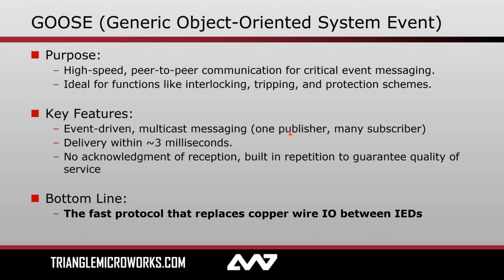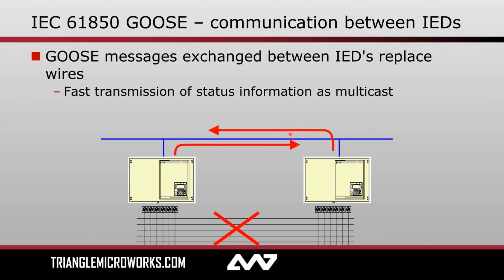But the bottom line, the thing that I hope you guys take away, if you haven't heard the term GOOSE before, is that this is a fast protocol that replaces copper wires by sending those same messages that used to go over a dedicated copper wire network, and now they're being passed over communications, right? So a lot less copper in the substation. Instead of having a dedicated wire for each signal we want to exchange between 2 devices, we now have maybe a fiber ring or some sort of communication network where we can pass these messages.